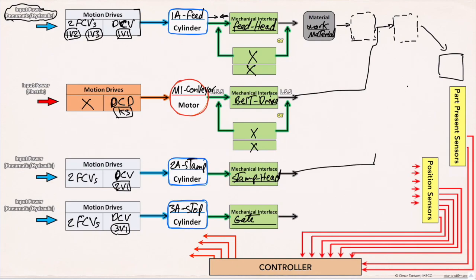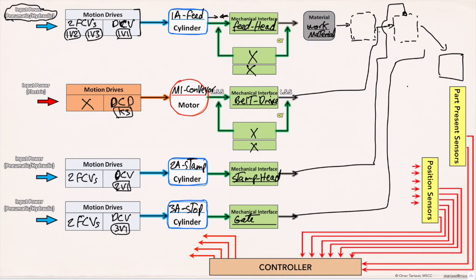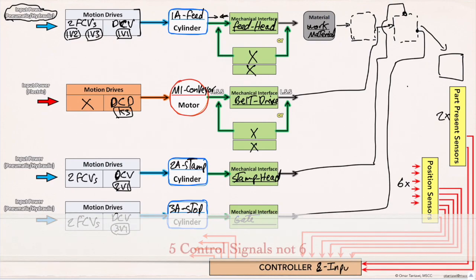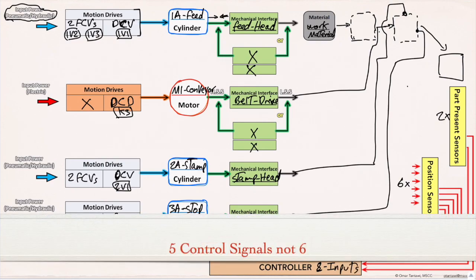Fourth step: specifying and drawing the feedback blocks. There are a total of six position sensors located on the three cylinders, and two part presence sensors located in the field. The fifth step is the controller I/O terminal block. A total of eight feedback signals are connected to the controller as inputs, and five control signals as outputs from the controller to the motion drives — a control signal for each solenoid or coil.